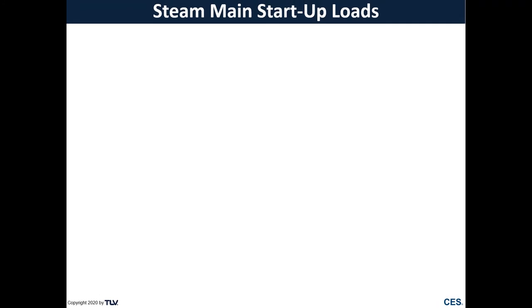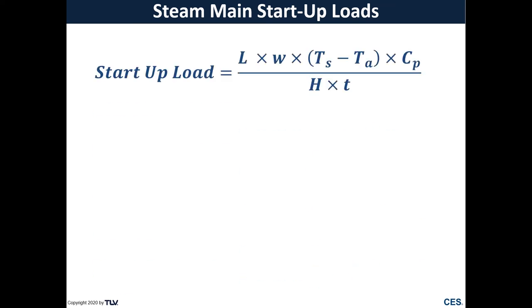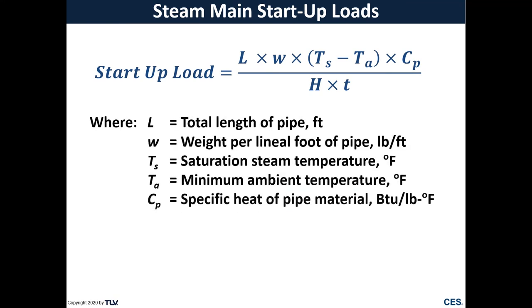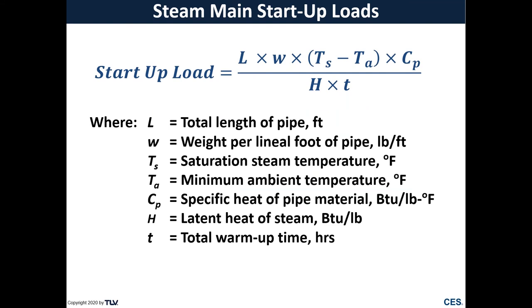So now we can look at steam main startup loads. These startup loads are going to be significantly higher than our normal operating loads because we need to heat up the entire mass of pipe in our steam distribution system. So we could look up this equation and find all of these variables, looking up the specific heat of our pipe material, the weight per linear foot, and many other things.